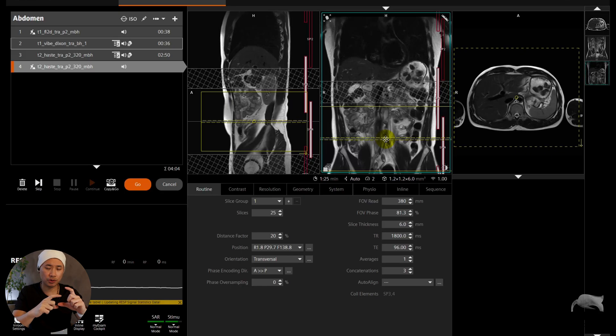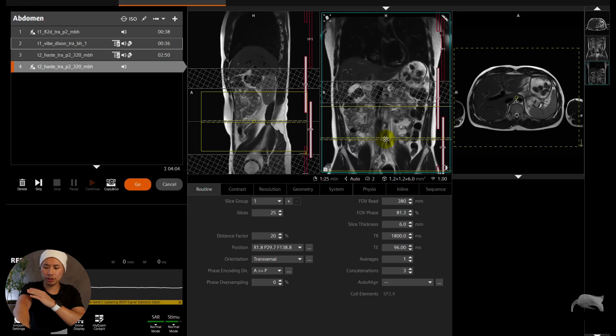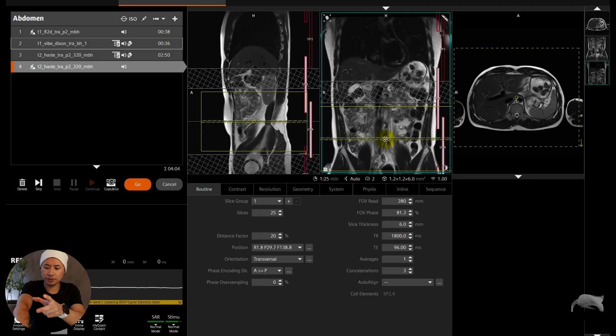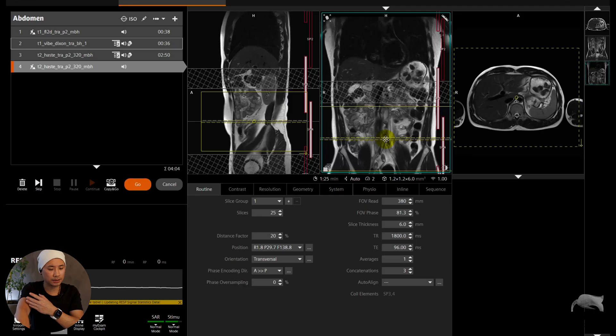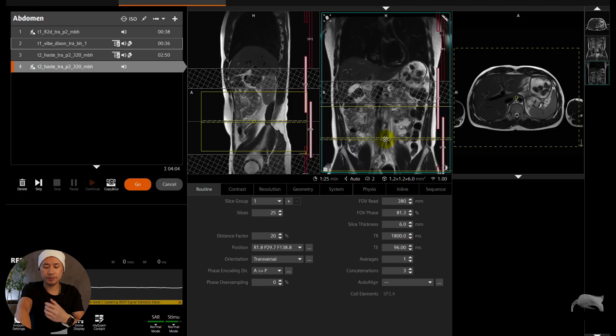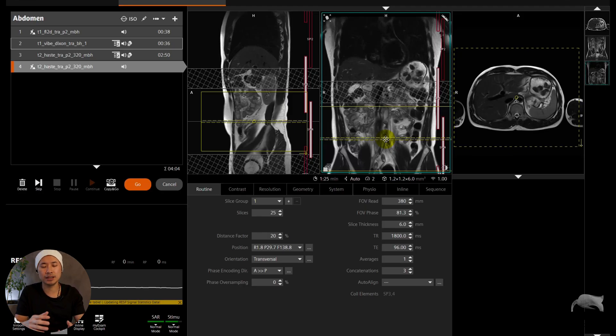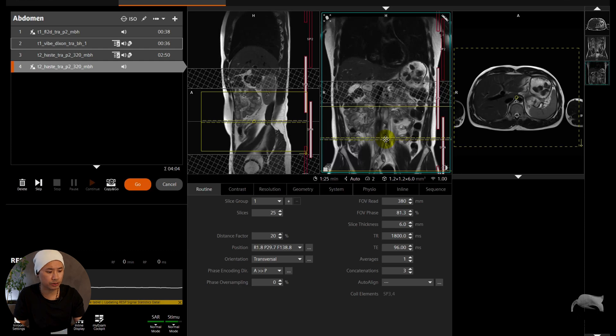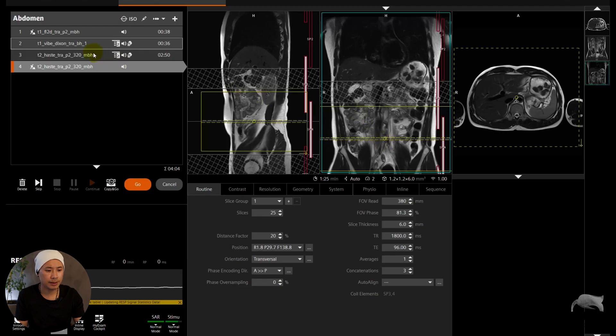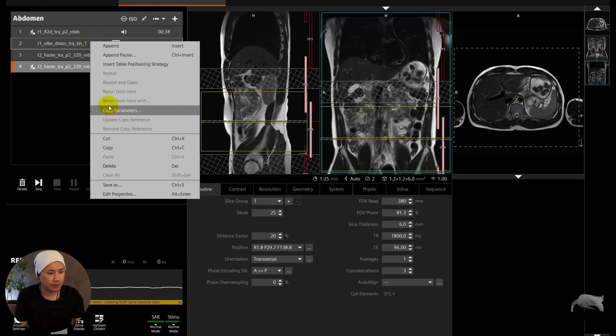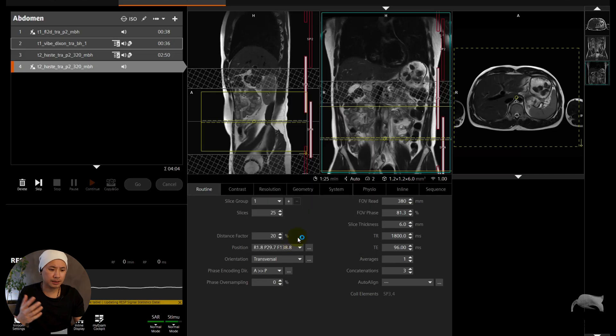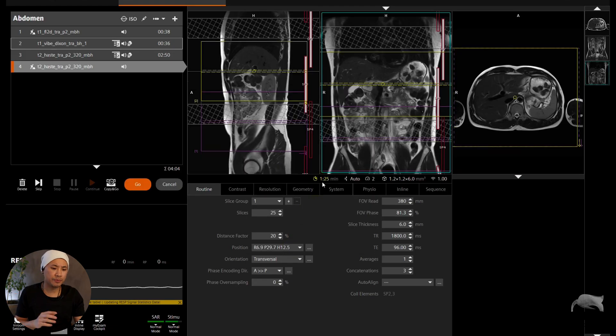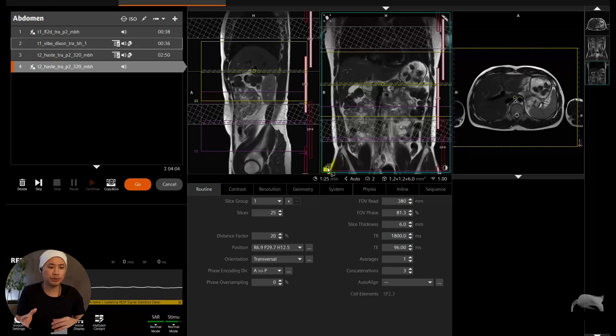You see, it's only copying one of that step, in this case the lower step. So what you really want is you want to have both of them all together, right? This is important if you do a long bone of the arm. You have multiple field of views, multiple transversal step boxes, and you want it to be all lookalike from a T2-weighted, from a STIR-weighted, from a T1, and so on. So this is the way you can do it much faster and making sure that the coverage is correct. So again, right-click, Copy, and push on the Steps. That's it. And remember to turn on the Inline Composing and it will automatically compose for you.